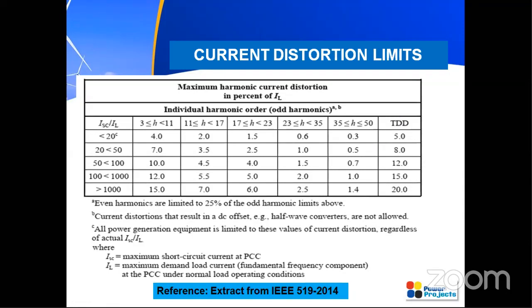And one important thing is that if you are checking either voltage distortion limits or current distortion limits, if your THD is well within the limits, then no need to worry about it. But if your THD exceeds the limits, then definitely you have to go for either an active filter, a passive filter, or a hybrid filter. You have to suppress the harmonics at the point of common coupling. So this has to be taken care of.